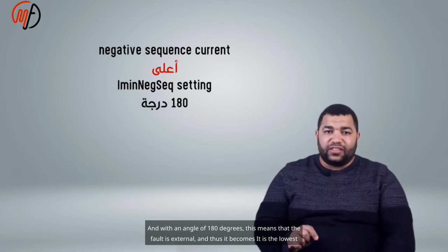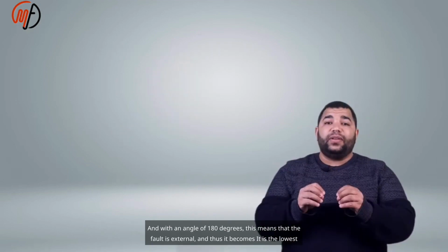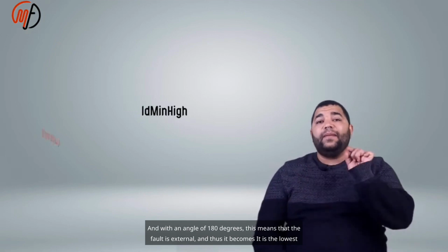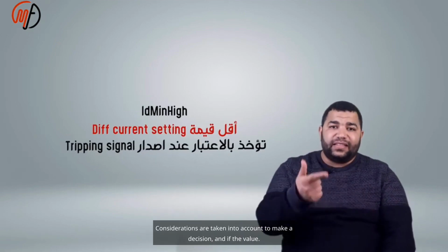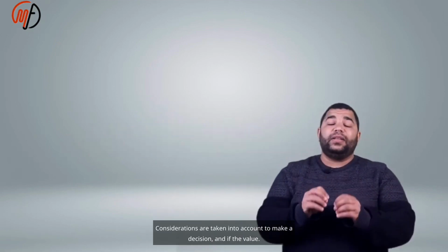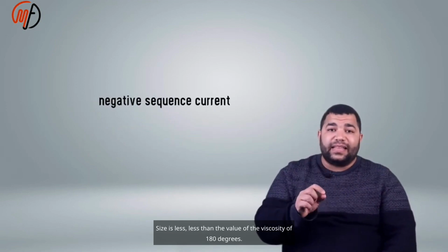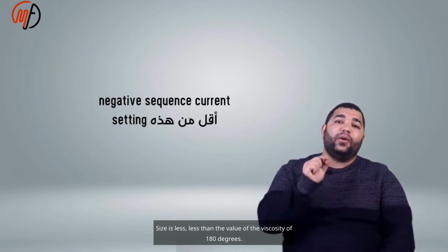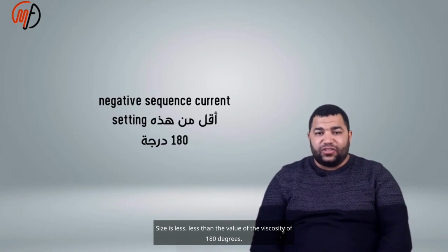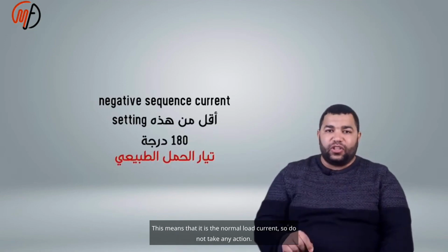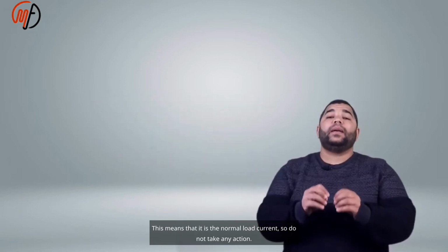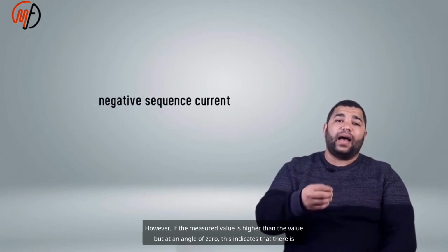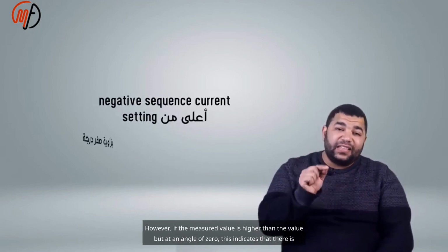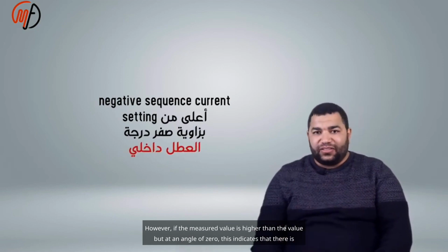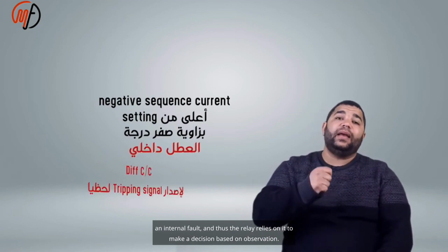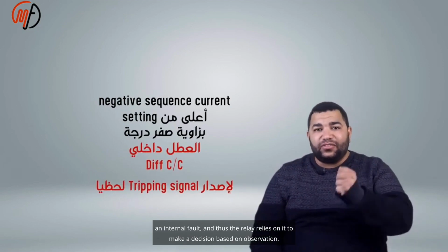And with an angle of 180 degrees, this means that the fault is external, and thus it is the lowest value considered to make a decision. And if the value is less than the setting at an angle of 180 degrees, this means it is the normal load current, so do not take any action. However, if the measured value is higher than the setting, but at an angle of 0, this indicates that there is an internal fault, and thus the relay relies on it to make a decision.